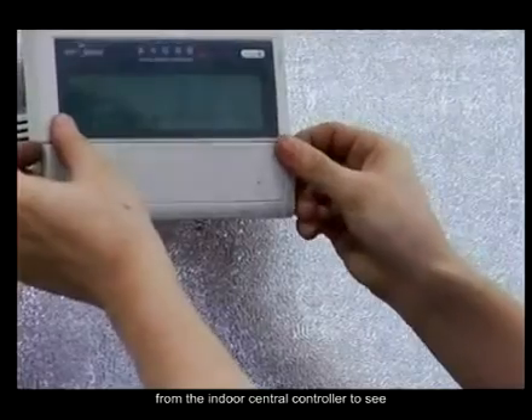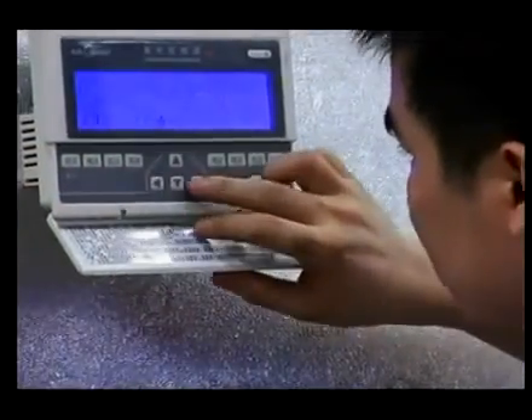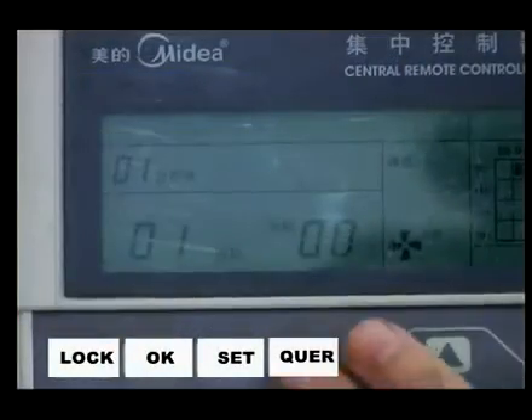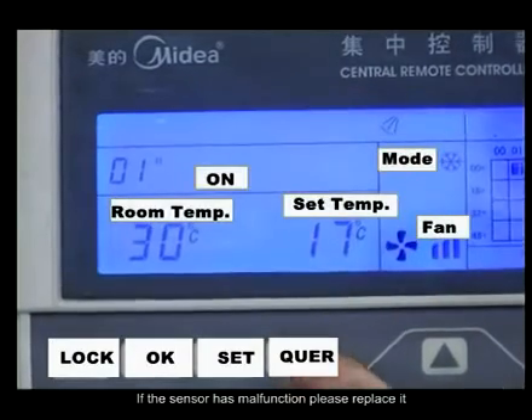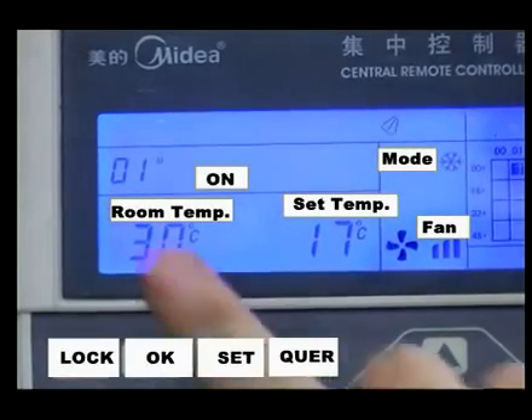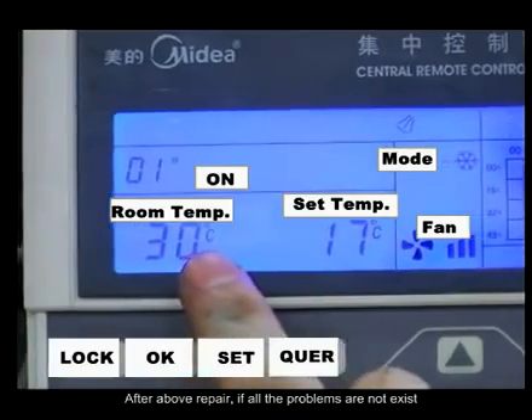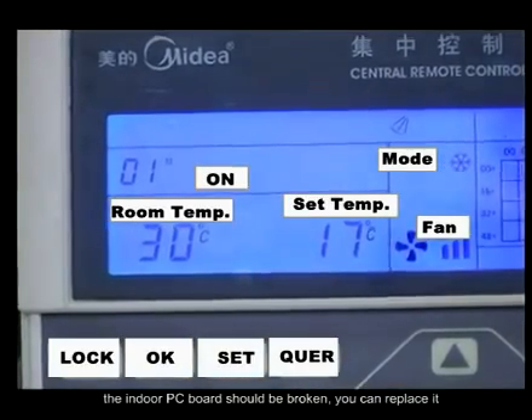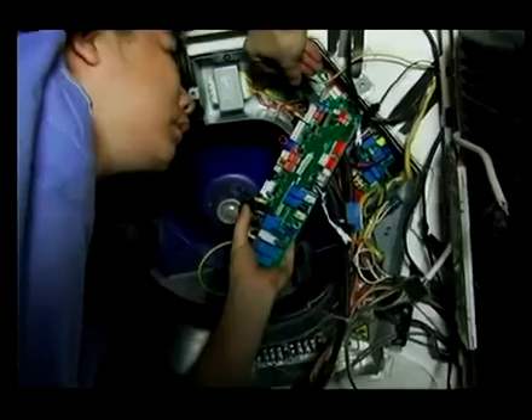You can also query temperature sensor T1 from the indoor central controller to see if it has reached the setting temperature. Check if the temperature data collected by the sensor has deviation. If the sensor has malfunctioned, please replace it. After the above repairs, if the problem still exists, the indoor PC board may be broken, and you can replace it.